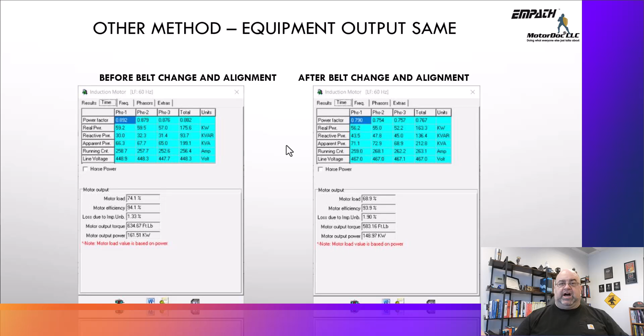I had done this also at a plant at General Motors - the savings were huge, measured and everything, so I knew this was going to happen. So we did that switch: 175 to 163, that's 12 kilowatts. Not minor - 12.5 kilowatts is $9,000 in energy, which meant almost immediate payback on everything. And 52.4 tons of CO2 - that's what sold the project.